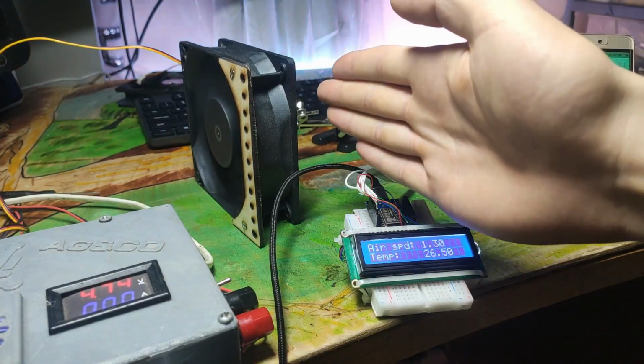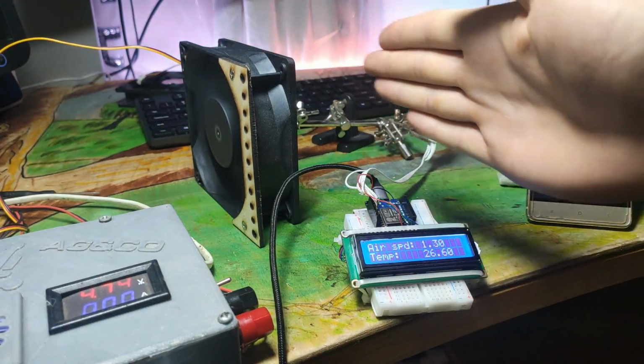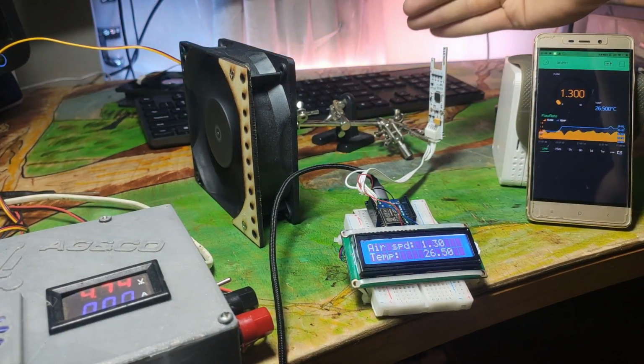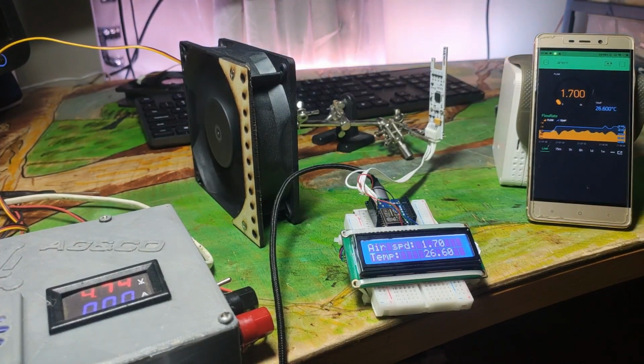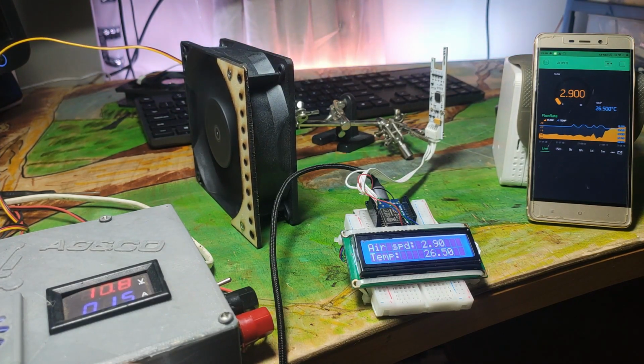Your device should be positioned perpendicular to the airflow, similar to mechanical anemometers with rotating blades. The controller side should be the side facing the airflow. To install the sensor in the ventilation pipe, it's enough to drill a hole of at least 20 mm in diameter, equal to the board width.